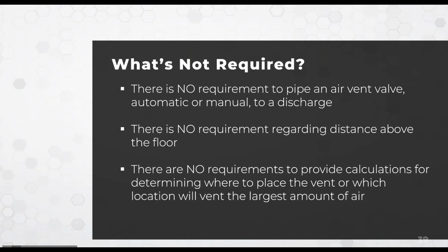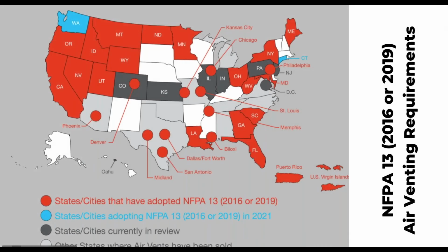Like you can't say, we'll put it at the highest point in the system. The problem is if you put the word highest, that's why the code says near a high point, not highest. Highest may be a poor location for it. It could be very inconvenient to get to. It could be just a bad area for the unit to work effectively. And then last, you're not required to perform any discharge calculation to know how much air you've gotten out versus how much water you've let in. There is no direct percentage of air volume to water volume calculation that you're required to do.